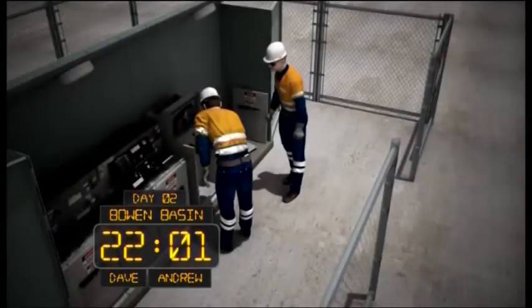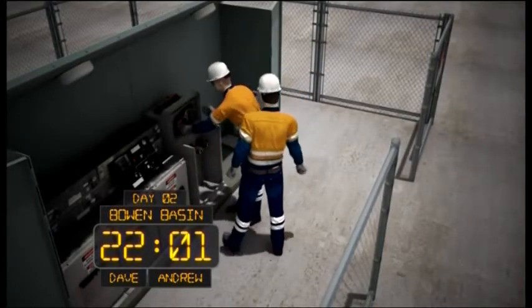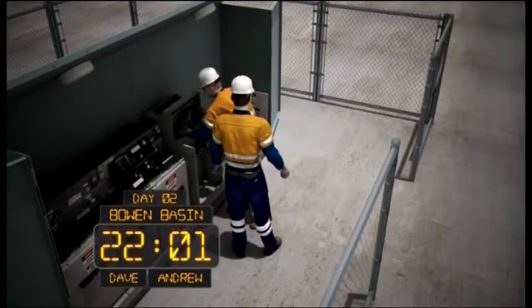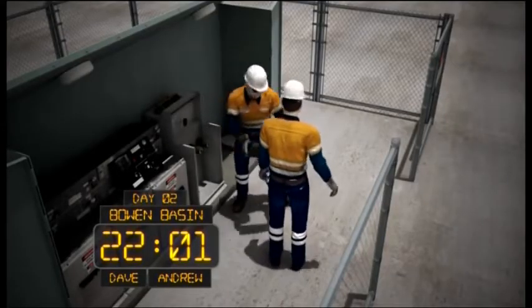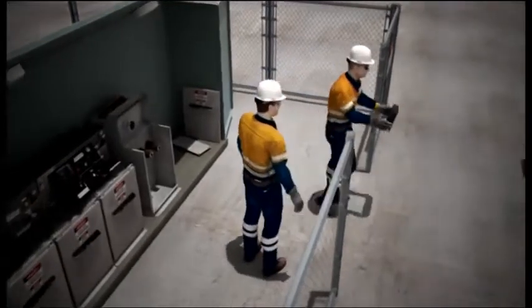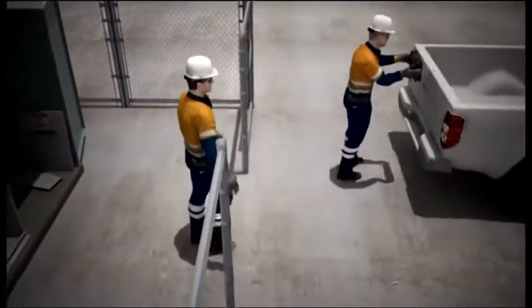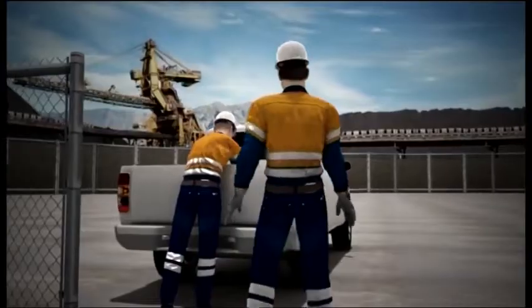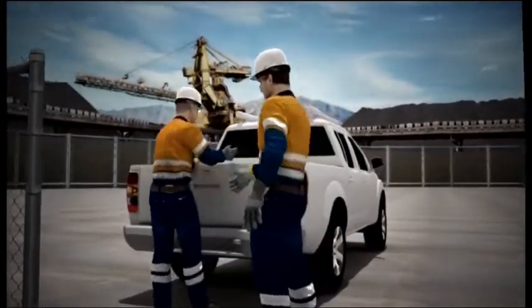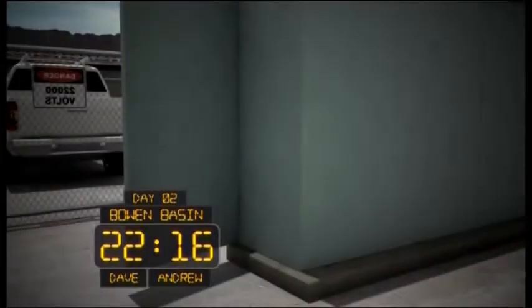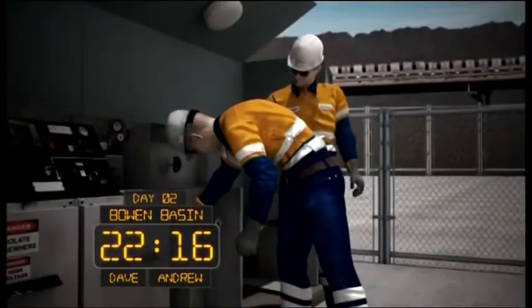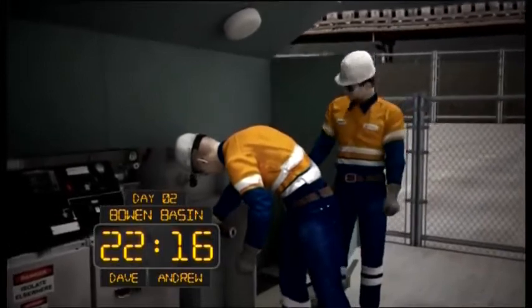Thinking it is safe to proceed, they defeat the mechanical interlock and remove the switch from the control shaft that operates the isolation mechanism. They then load the switching mechanism onto the back of Mark's vehicle so he can take it back to the workshop. Dave and Andrew start to reassemble the HV cabinet just as Mark drives off. Andrew reaches inside the cabinet to replace the mechanical interlock.